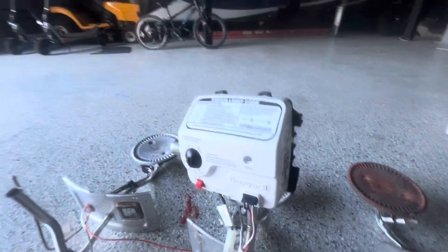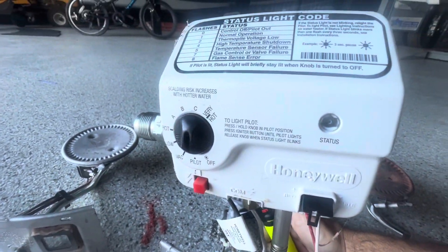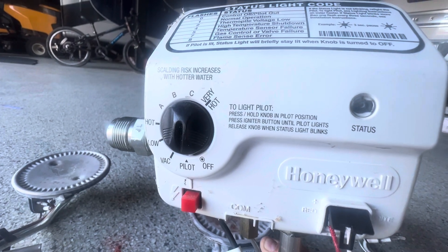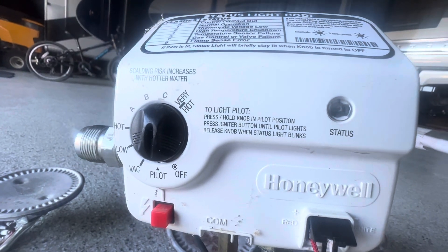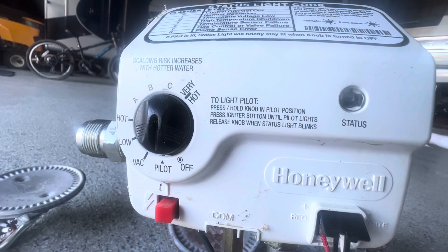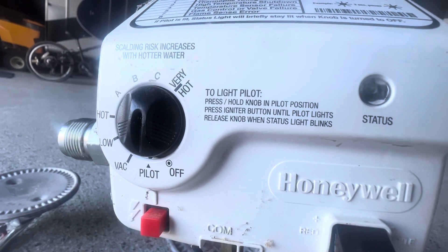I'm going to show you this real quick. I'm going to take a lighter and start heating up the thermopile. When it gets up above a certain range in millivolts, the valve will kick on and that light will start flashing. And there it goes.